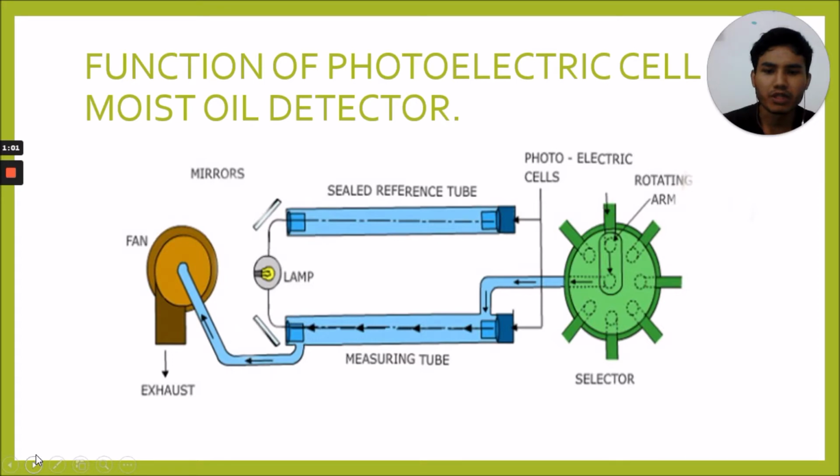One of the tubes contains clean air and is called the reference tube. The other tube has a connection through which the vapor of the crankcase is drawn by means of an electrically driven extractor fan. Sampling points are normally fitted to each cylinder crankcase and their connections are led to a rotating selector valve which repeatedly connects each sampling point to the measuring tube in proper sequence.